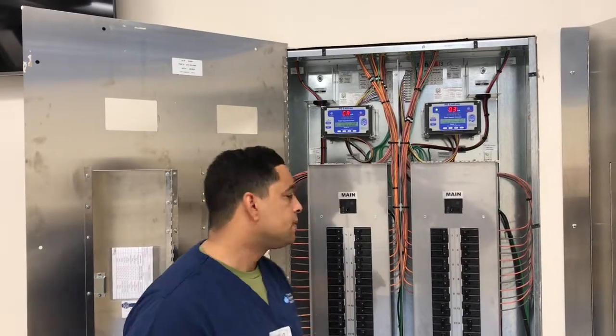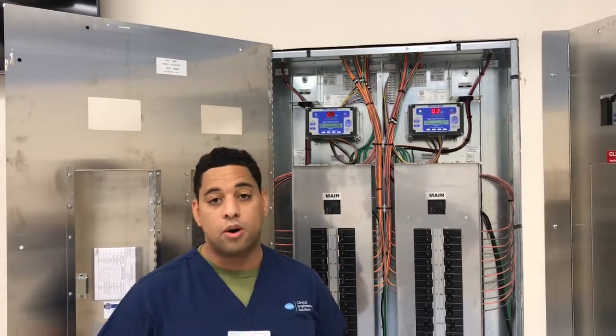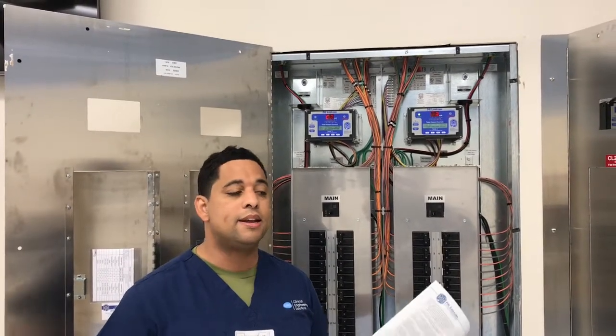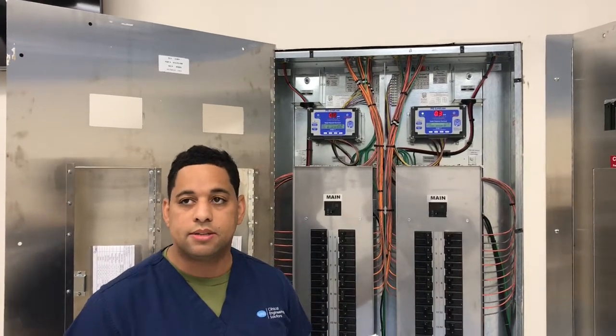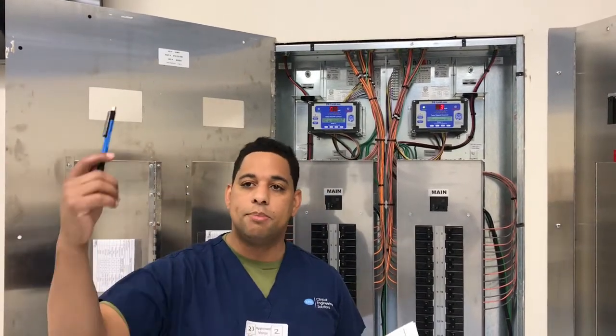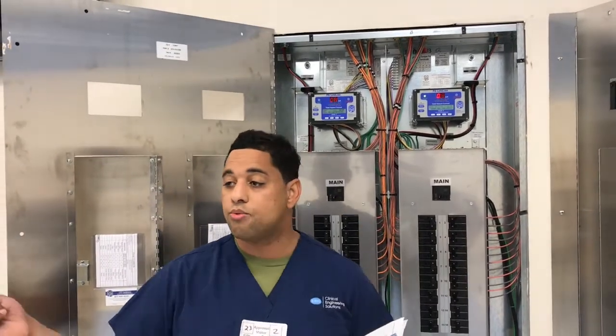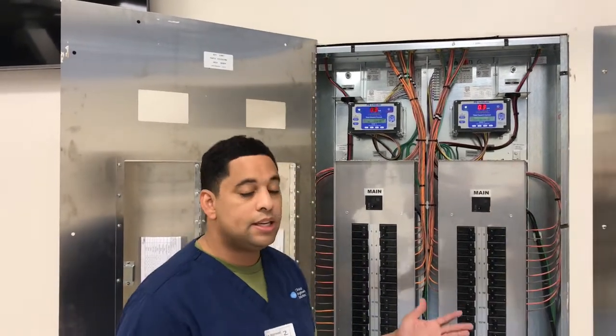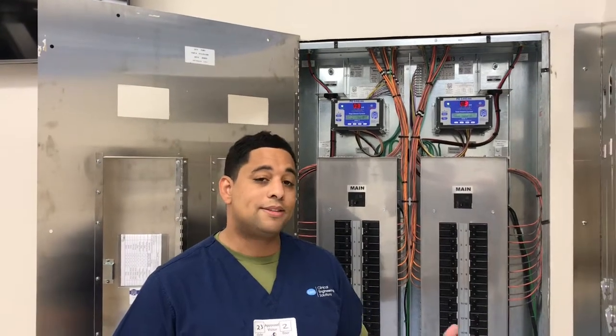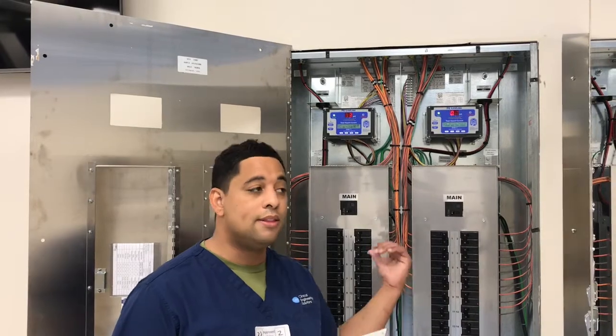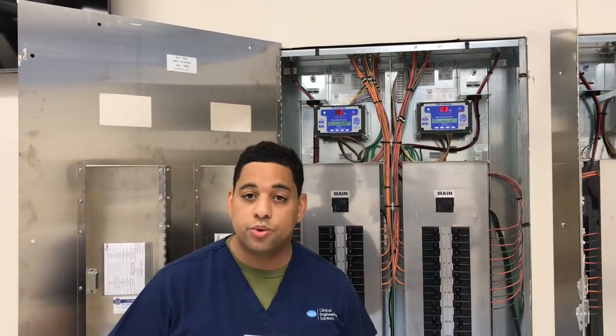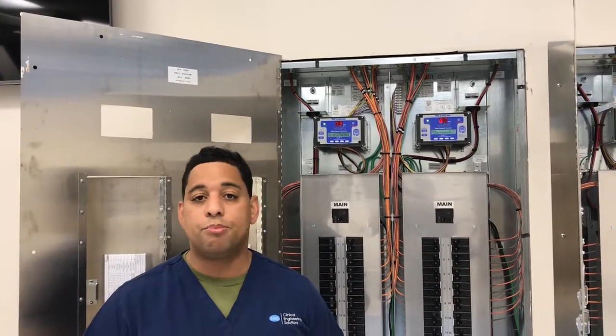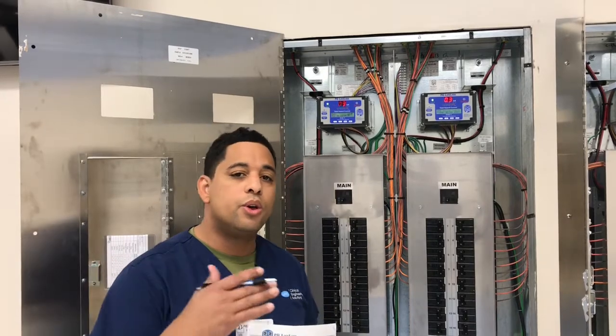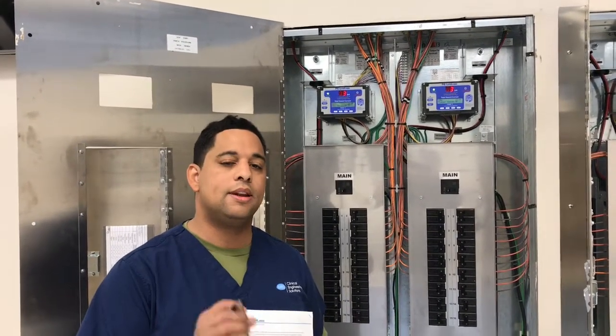Another key point to remember. These isolated power panels are meant for electronic devices being used in and near the patient for obvious reasons. And so all of the lighting, your booms, your monitors are connected to it. So are the red outlets in the room. I don't see any white outlets. That would be an alternative, maybe one, but we often tell facilities to try to avoid using equipment that's not patient related in the room or in the isolated power. For example, radios, amplifiers, printers, computers. If you're going to use those things, use those on normal power, the white outlet, not the red outlets.